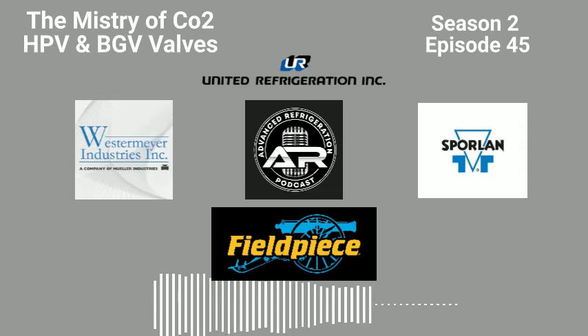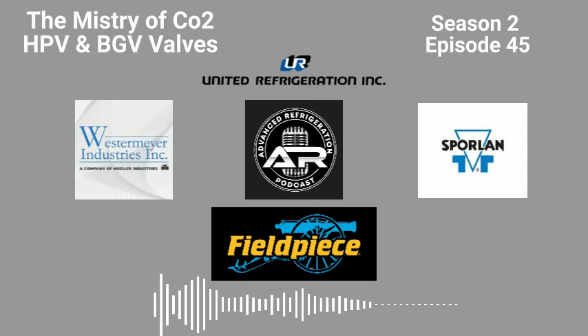So some of them I've been changing to CDS valves. Certain manufacturers said they had a failure. I'm going to be honest, I haven't lost a CDS valve yet. You just figure out the size of the valve that was in there and then change it out with a Sporlan CDS valve. Generally a CDS 7 or 4. I haven't seen bigger than a CDS 7, even on a bigger rack. Thank you, Sporlan. They end up working good.